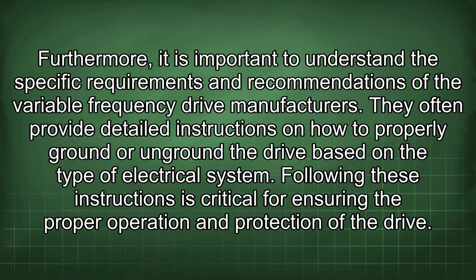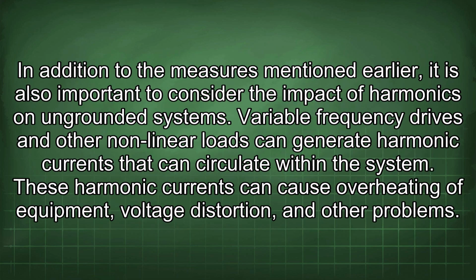Furthermore, it is important to understand the specific requirements and recommendations of the variable frequency drive manufacturers. They often provide detailed instructions on how to properly ground or unground the drive based on the type of electrical system. Following these instructions is critical for ensuring the proper operation and protection of the drive. In addition to the measures mentioned earlier, it is also important to consider the impact of harmonics on ungrounded systems. Variable frequency drives and other nonlinear loads can generate harmonic currents that can circulate within the system. These harmonic currents can cause overheating of equipment, voltage distortion, and other problems.